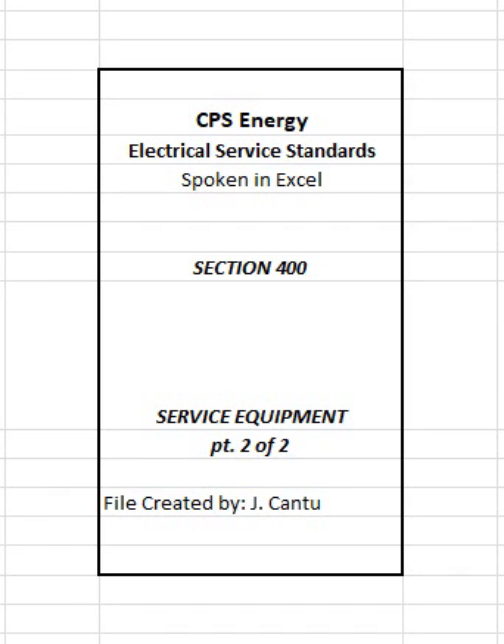405.1 One readily accessible location. The service disconnecting means shall be installed at a readily accessible location either outside of a building or structure or inside nearest the point of entrance of the service conductors. Exception 1. 1 and 2 family dwellings shall have the service disconnecting means located on the outside of building at the CPS Energy approved meter location, refer to section 700.